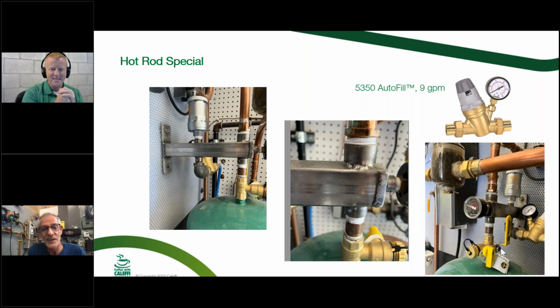Well, limited or mixed results, but now that you brought that up, I think Amtrol, they're coming out with a new tank with a clear plastic cap, it looks like, that goes on the bottom, and you screw that tight, and it must push the Schrader valve, and it's an indicator. If your bladder's failed, it turns colored. If it's rusty, it turns red colored. So I guess that's, in between pushing it in with your finger or rapping it with your knuckles to see if it's waterlogged or shaking it. Everybody's got a different method to see if it's waterlogged. Obviously, if the pressure goes right up when you fire your boiler, that's another indication.